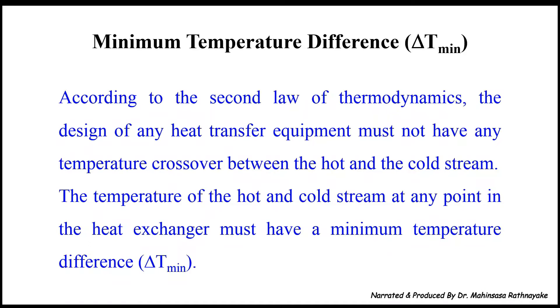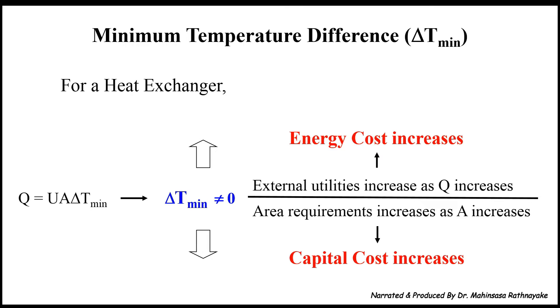According to the second law of thermodynamics, the design of any heat transfer equipment must not have any temperature crossover between the hot and cold stream. The temperature of the hot and cold stream at any point in the heat exchanger must have a minimum temperature difference. This minimum temperature difference is symbolized as delta T minimum. For a heat exchanger, we can use the governing equation Q equals U A delta T minimum. Based on this equation, delta T minimum cannot be equal to zero, because if it equals zero there is no heat transfer. When delta T minimum increases, the heat duty increases, meaning external utilities increase.